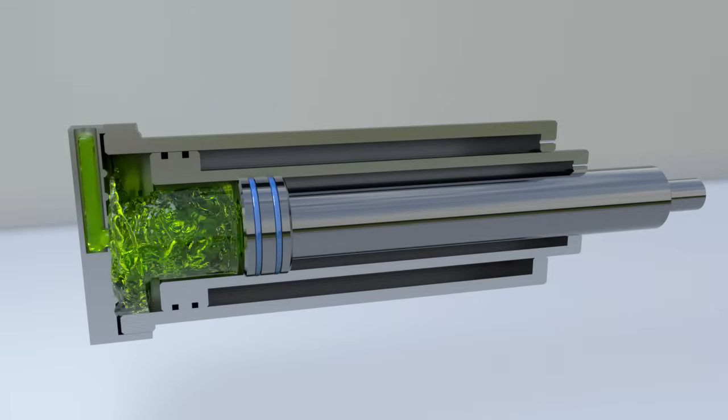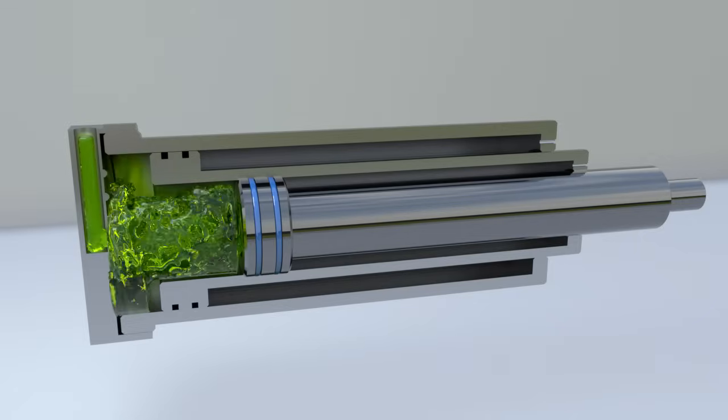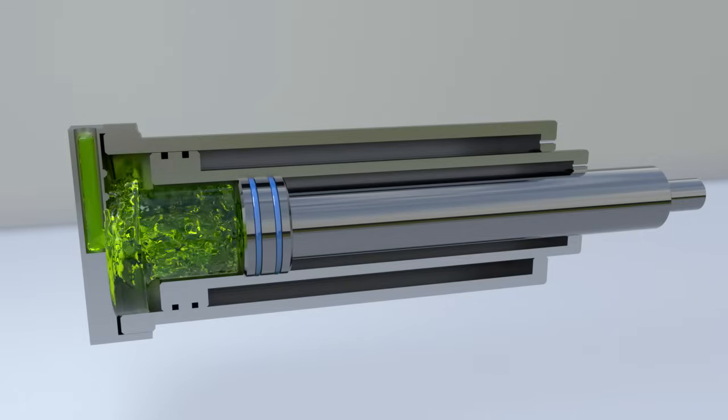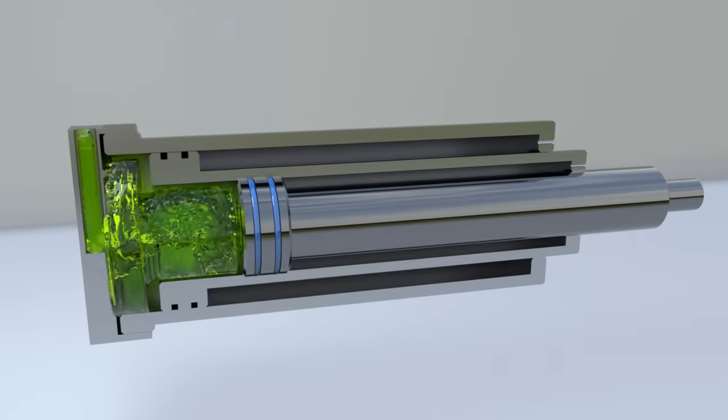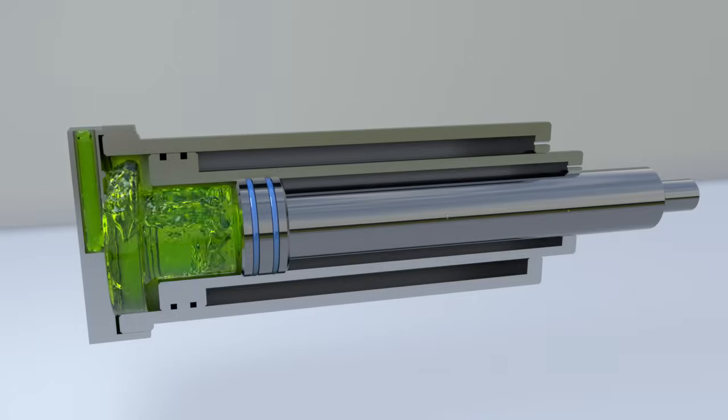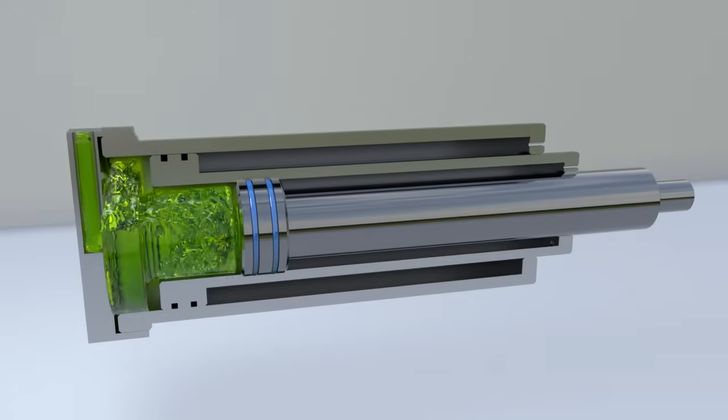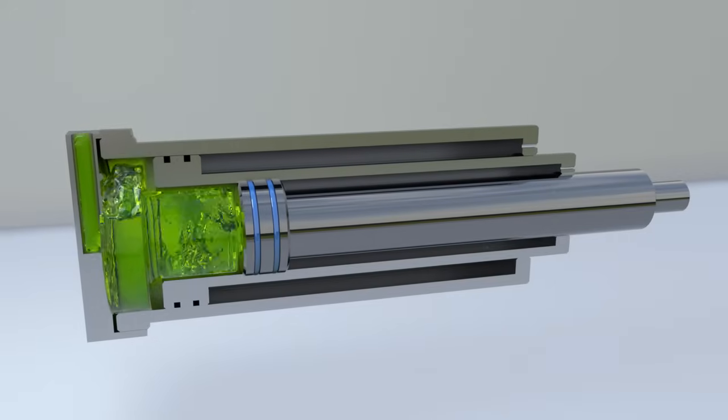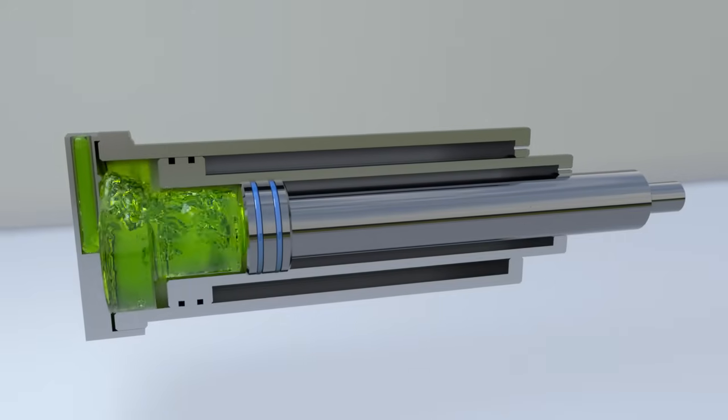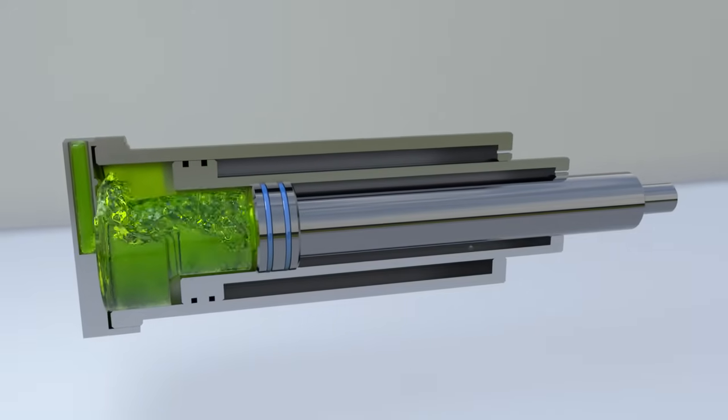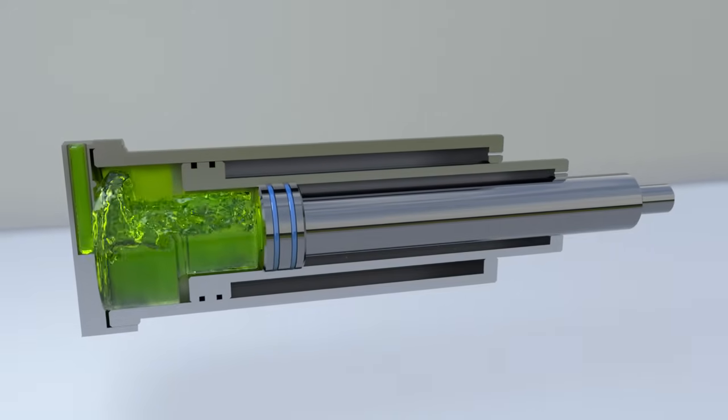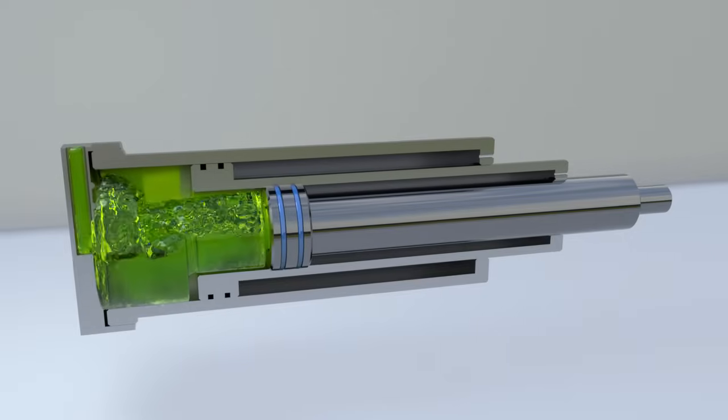Let's talk about the operation of a single-acting telescopic cylinder. When liquid is supplied, the largest section will extend first. When the first section has reached the end piston, the second one will extend, and so on.